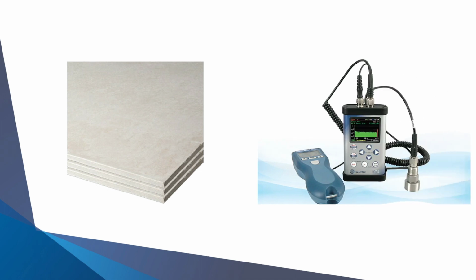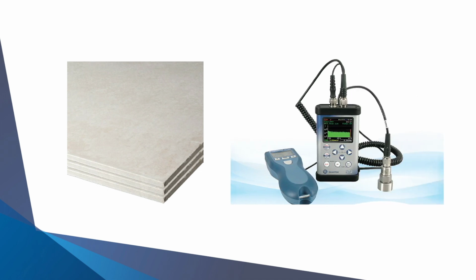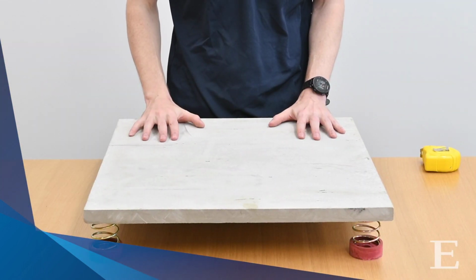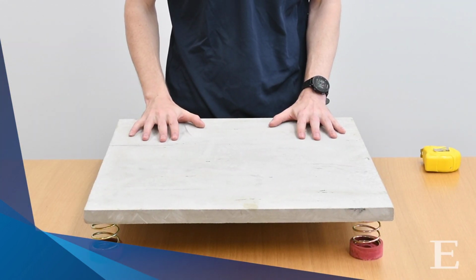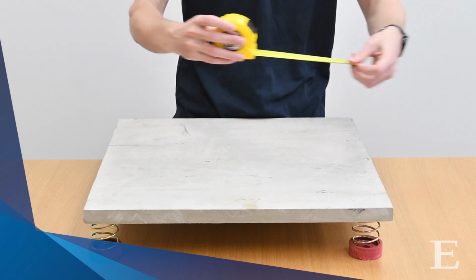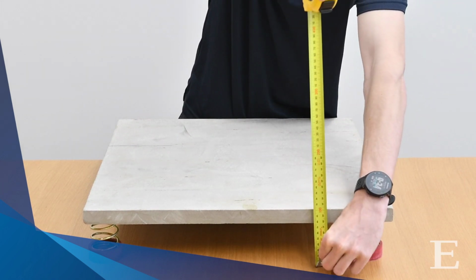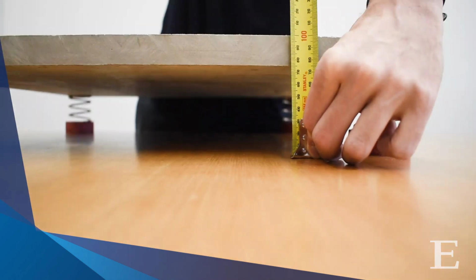We could get an accelerometer, which will give us frequency domain data. Not everyone has access to that either though. It's much simpler just to measure the static deflection on the mount, which immediately tells us what the stiffness to mass ratio is. So if I know that the free height of these springs is 82mm, I can take my tape measure, measure the deflected height, which comes out at about 75mm.